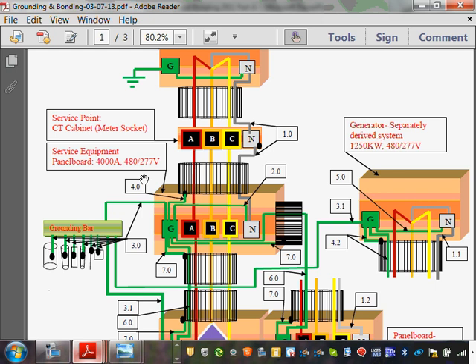You can't be approved if your impedance here to ground is not less than 5. If more than 5, they will keep at you driving ground rods everywhere until you're getting 5 or less. In the US, what do we have? 25 or less. 5 or less for telecommunication companies, they use it. Anyway, so that's why we don't bond the neutral. But we're in the US, so let's go to 2.0 and size the main bonding jumper.